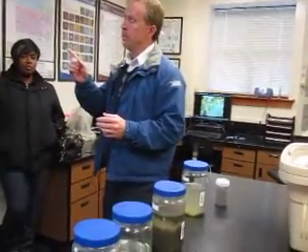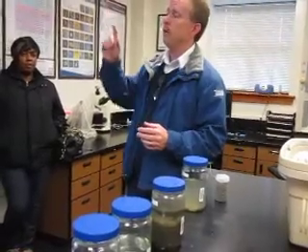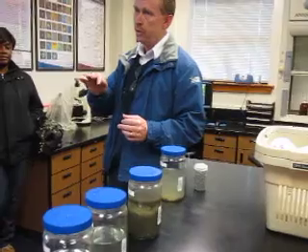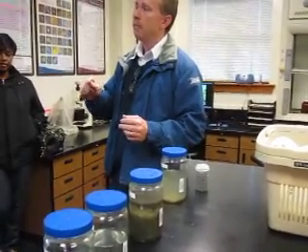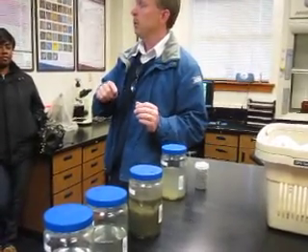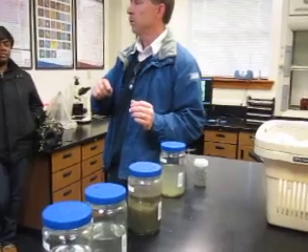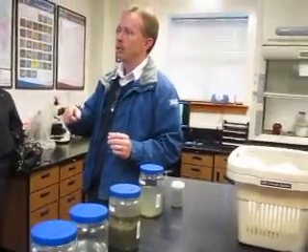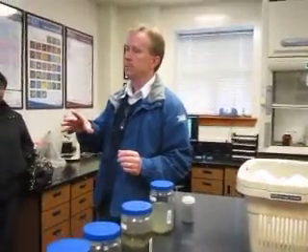The pH meter that we have up here at preliminary treatment is continuously measuring the pH. That measurement is pulled back into our plant SCADA system or computer system. As soon as it sees a 5.9, it's going to throw up an alarm on that computer system.